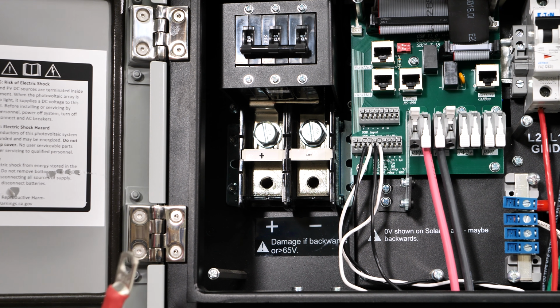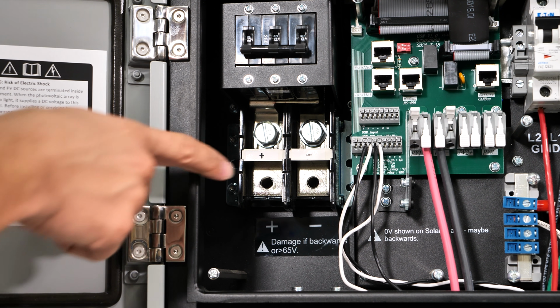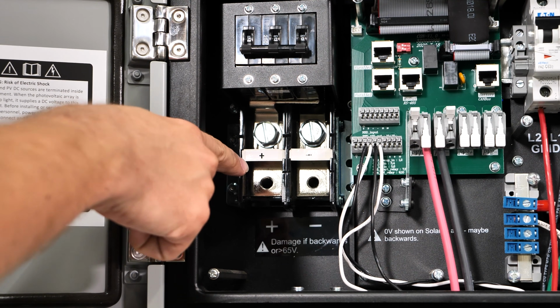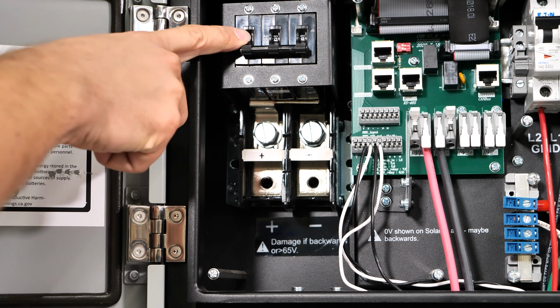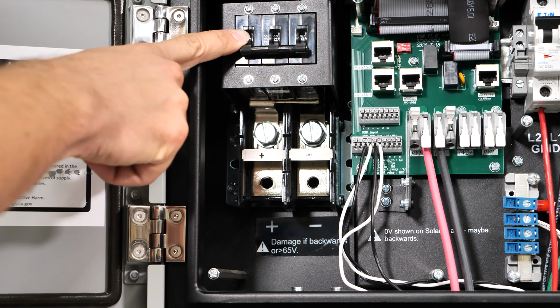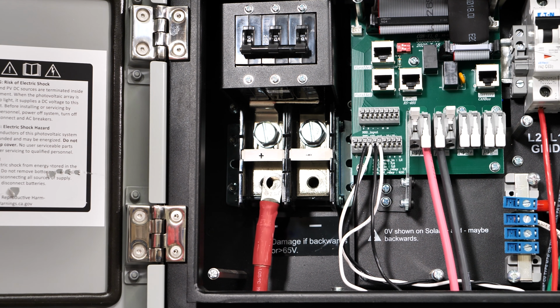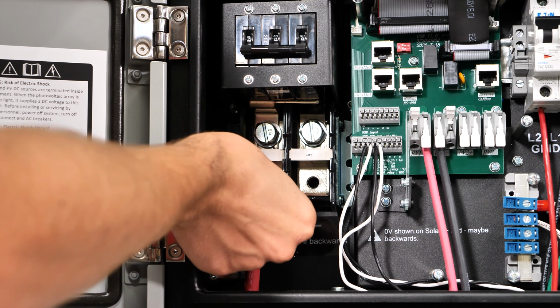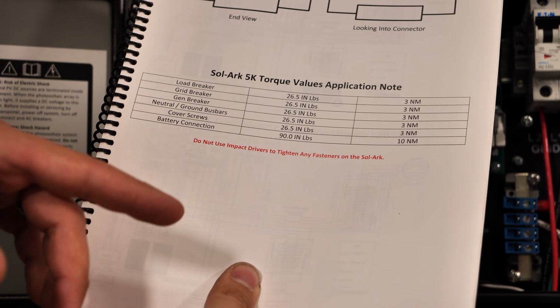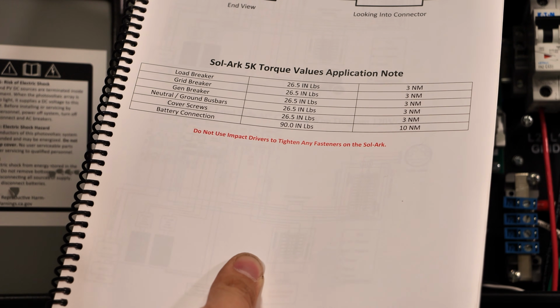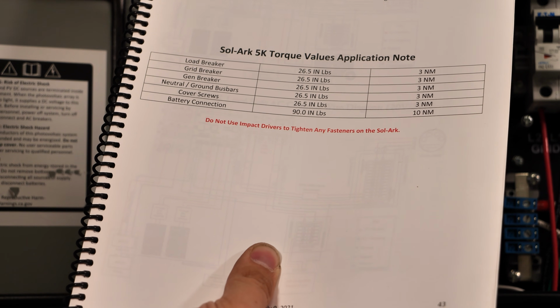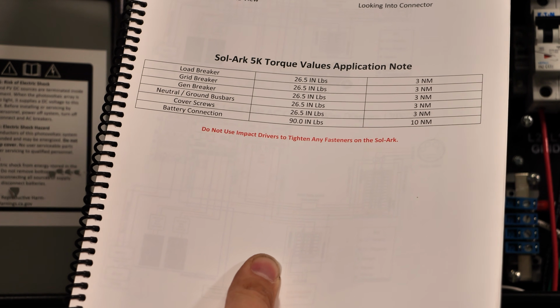We need to connect our battery cables to the Sol-Ark. So here in the Sol-Ark, this is where those connect on. We also have a DC disconnect here. You'll note that that is currently off. So our cable feeds in through the bottom, and then our bolts just thread into this terminal block here. And Sol-Ark conveniently provides us with the application note to tighten these connections to 90 inch-pounds or 10 Newton meters.